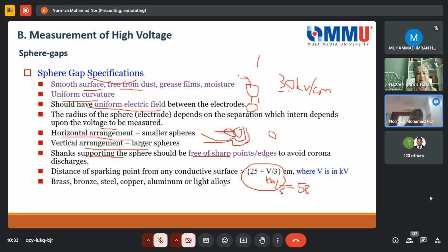So it means that if we apply it in high voltage testing, or if you go to a high voltage substation, that's why they put the equipment far from one another, because they use this clearance, or in other words, the distance of the sparking point. So if I put one equipment here at 30 kV, the person has to stay at least 1 cm away. But of course, this 30 kV per cm is the breakdown of air under ideal conditions. In reality, because of different atmospheric conditions, different temperature, humidity, all this, this 30 kV per cm is not normally used when we determine the distance of the sparking point.